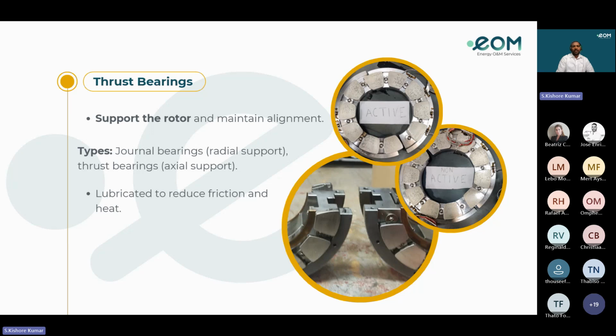Usually during the turbine startup, the non-active pads' temperature will increase. Once the turbine is loaded, the temperature in the active pads will increase. Here we can see the active and non-active pads supported by the sleeve, and here we can see the RTD, so we are able to read the temperature of the active and non-active pad thrust bearings.